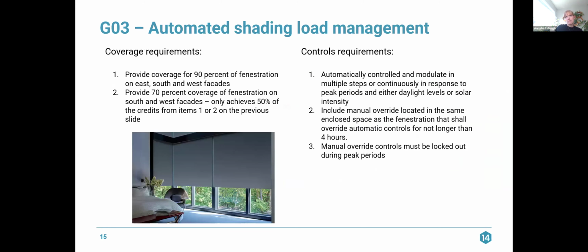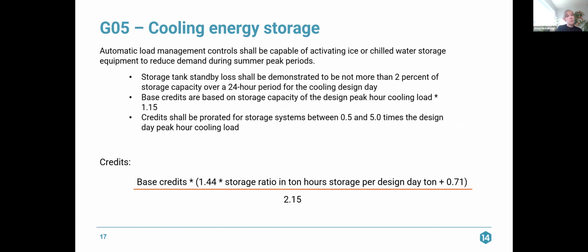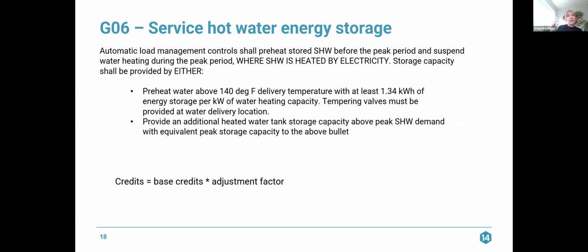Oh my gosh, cooling energy storage opportunity. Something that kind of grinds my gears about this is that you can use thermal energy storage for service hot water heating, but there is not a credit for heating hot water energy storage. So storing large tanks of heating water to reduce peak demand really frustrates me, because that's one of the more effective ways to reduce your peak demand in the winter when you have an electric boiler or a heat pump chiller that's creating your heating water with a backup electric boiler. Maybe it's something to consider for the next update.